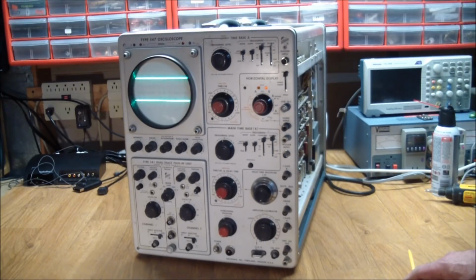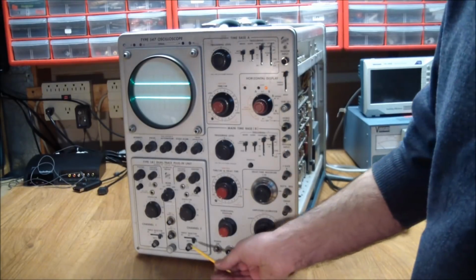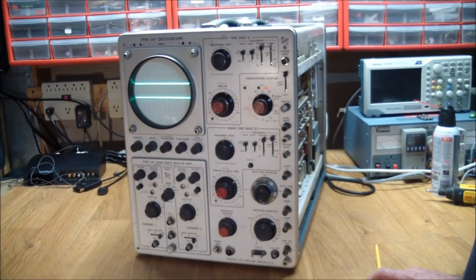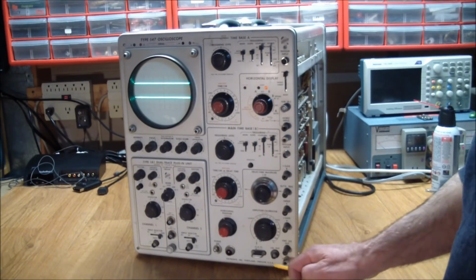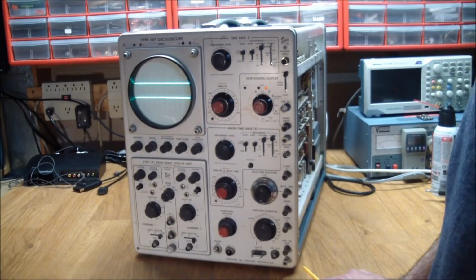So the delay part just kicked in, and now we've got to wait for it to warm up a bit. And what I'm getting is, of course, with the crappy camera I'm using, it's not showing the traces in their full glory, but what we're looking at are typical Tektronix high-quality razor-sharp traces. Both channels are set to ground right now. Doesn't mean much.